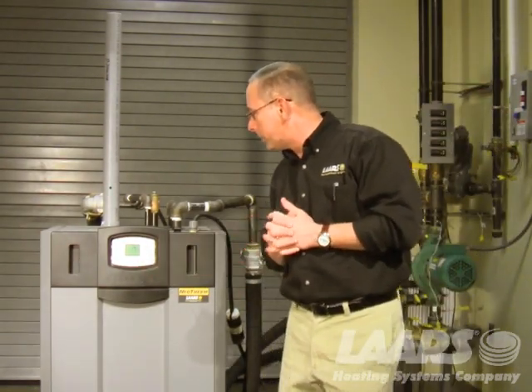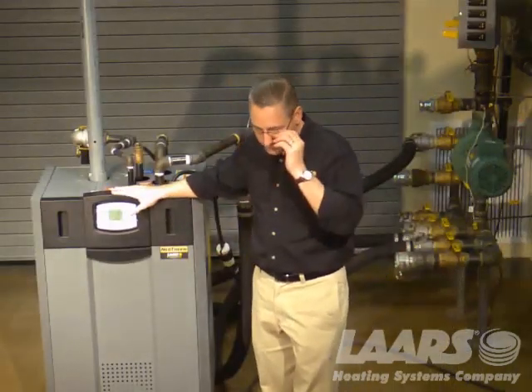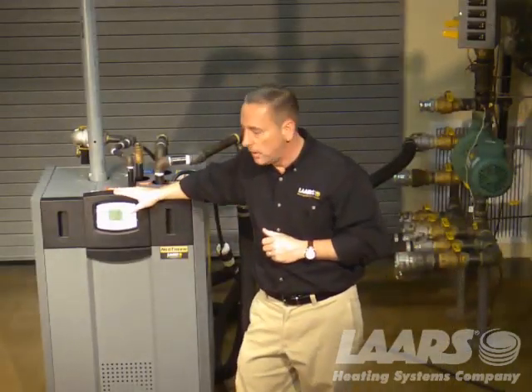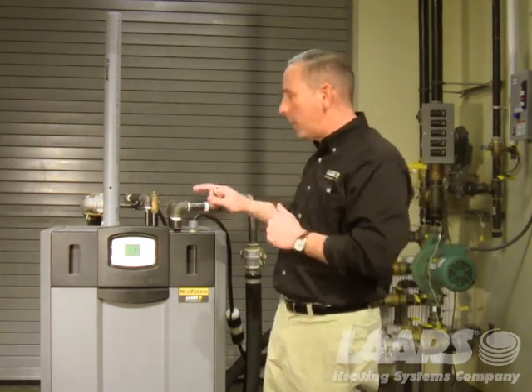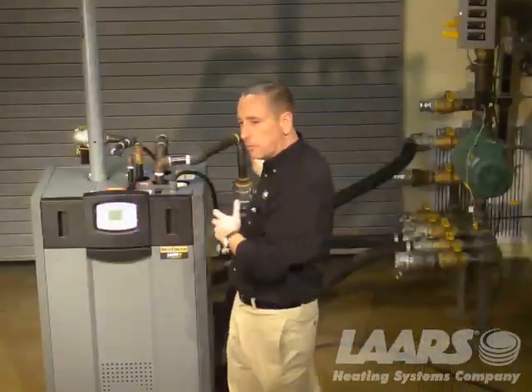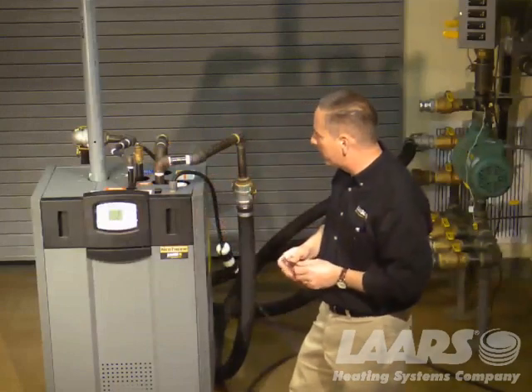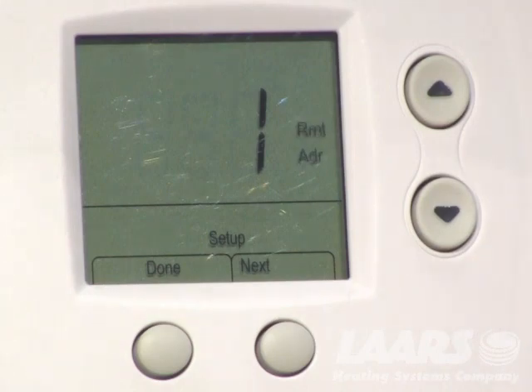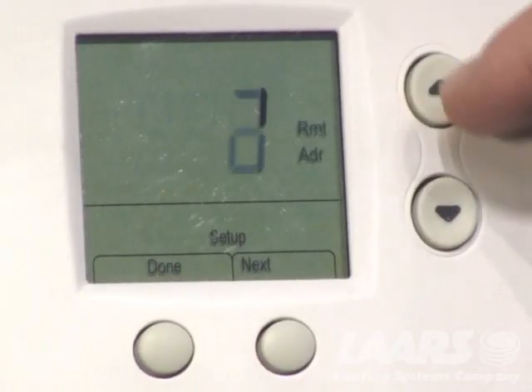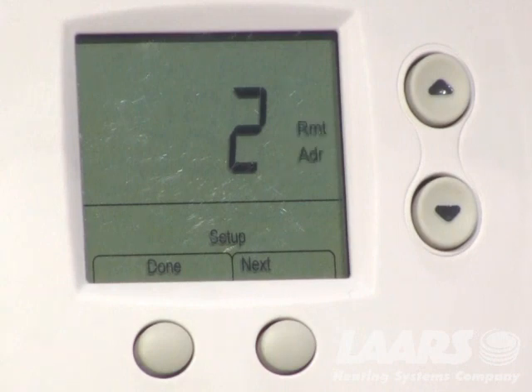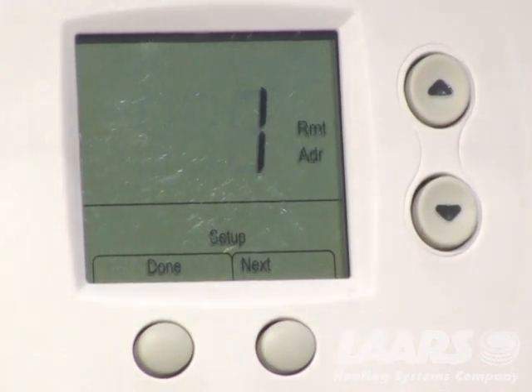Press next again — this is remote address. A single standalone boiler should always have a remote address of one. If you're cascading boilers — you can daisy chain up to eight boilers and operate them from one master boiler — the lag boilers become slaves. On a single standalone boiler, always use an address of one. If cascading with two boilers, use the up arrow and choose two for the second boiler. The first or master boiler is always address one.